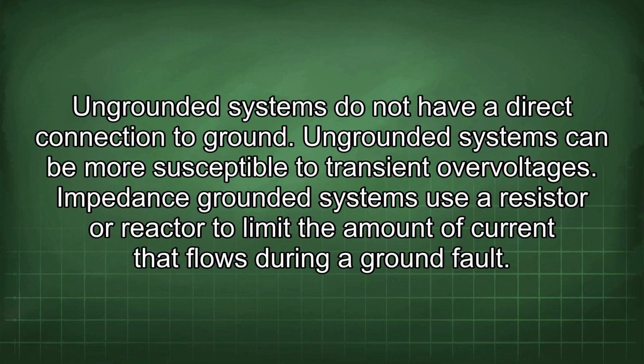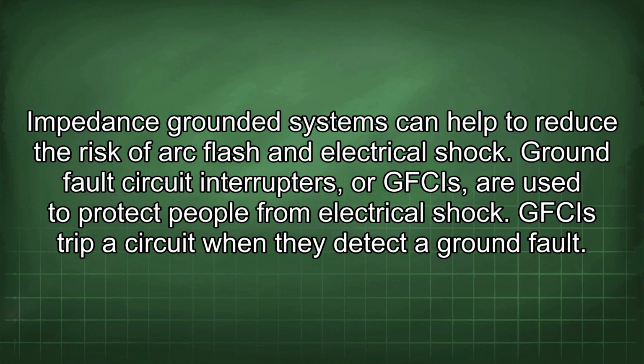Ungrounded systems do not have a direct connection to ground. Ungrounded systems can be more susceptible to transient overvoltages. Impedance grounded systems use a resistor or reactor to limit the amount of current that flows during a ground fault. Impedance grounded systems can help to reduce the risk of arc flash and electrical shock.